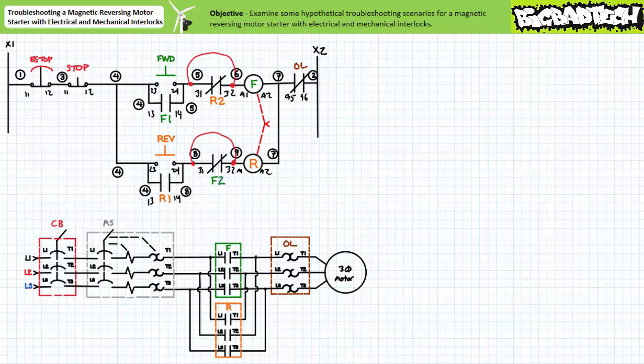While a magnetic reversing motor starter with only a mechanical interlock does prevent simultaneous closure of both contactors, it does so at the risk of potentially damaging the contactor coils. For this reason, magnetic reversing motor starters with both electrical and mechanical interlocks are preferred.